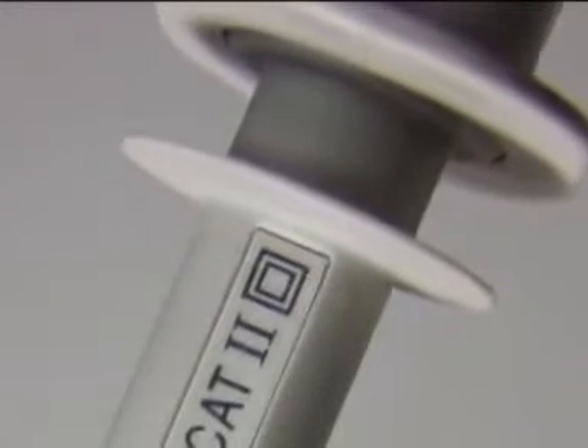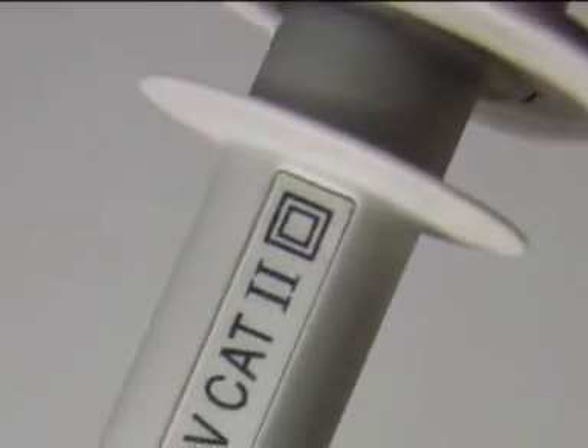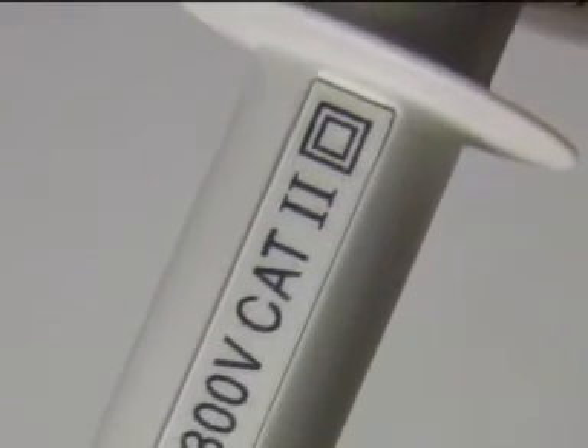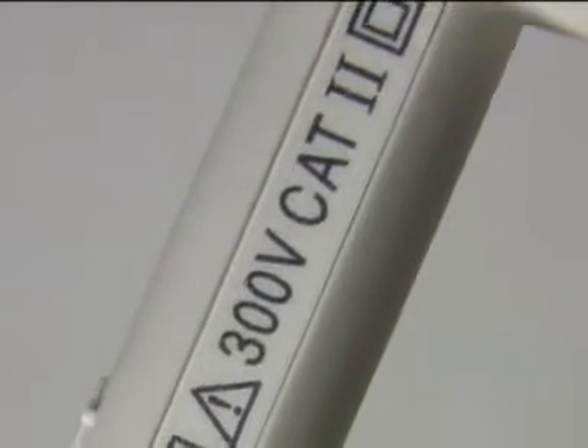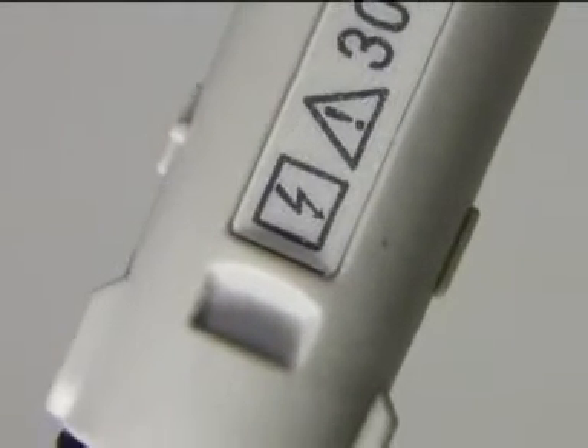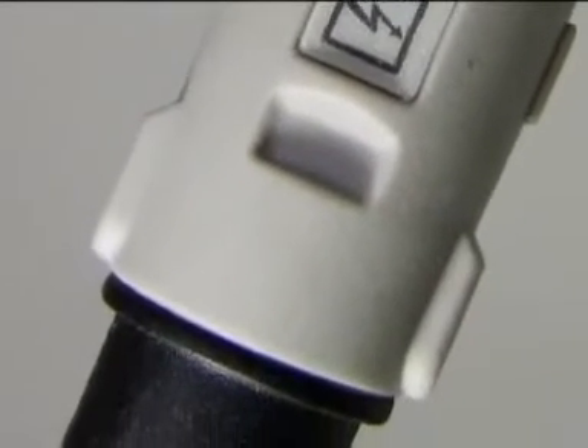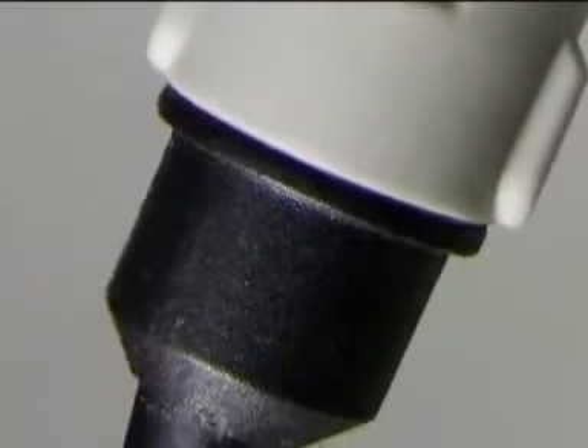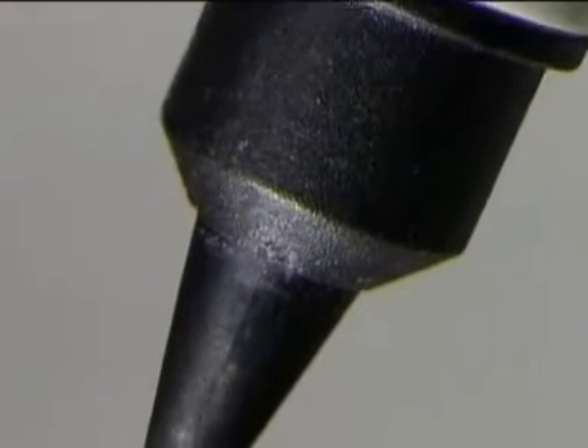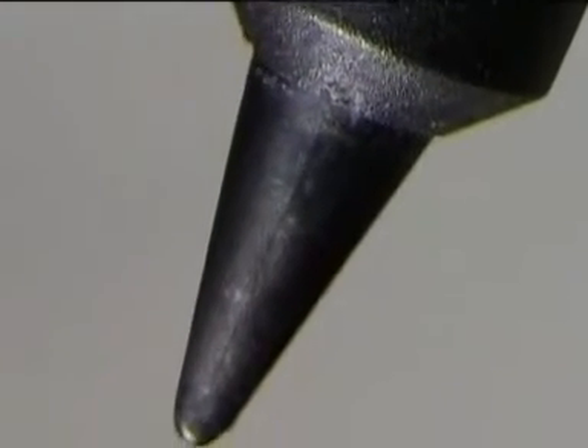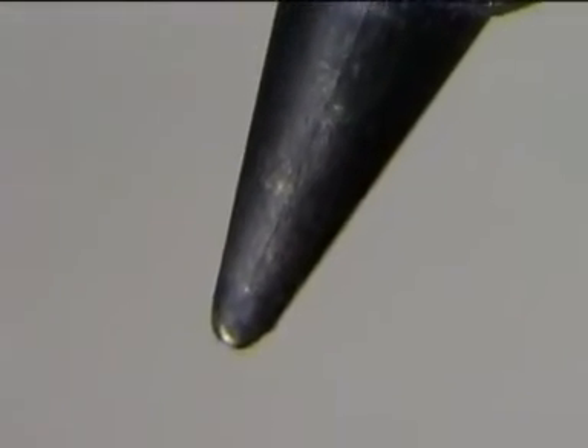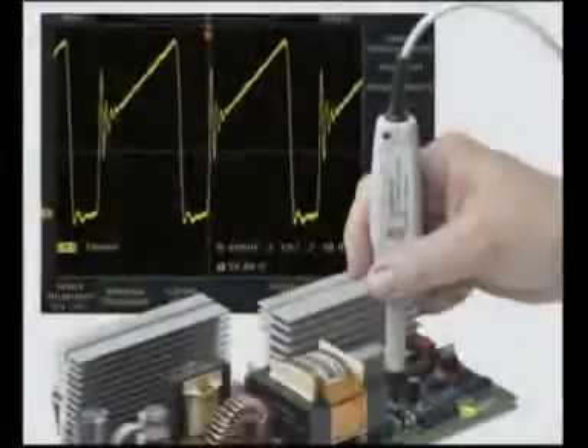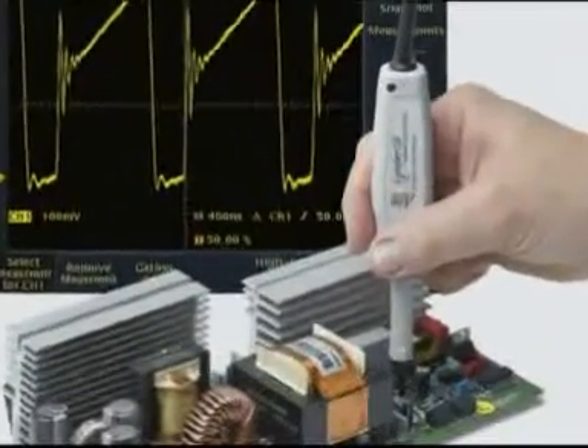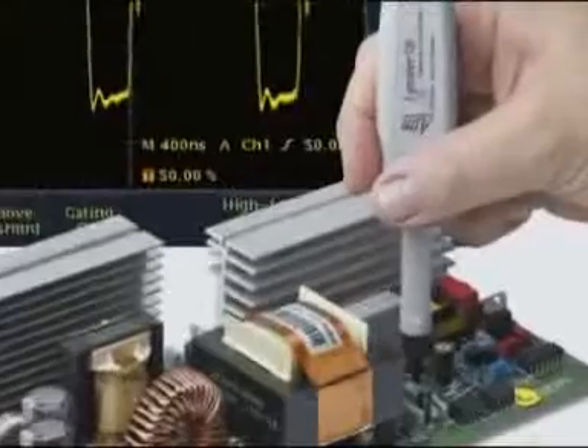So what's inside an iProber that makes this type of measurement possible? The heart of the probe is a patented miniaturized version of a fluxgate magnetometer. Fluxgate magnetometers have been around for decades, but not in miniature form. It is the patented miniaturization that enables it to measure the field at a precise point in space. But in addition to that, the miniature sensor has a much lower noise and much wider bandwidth than a conventional fluxgate magnetometer. Users must consider all fields that will be present in the area of the probe tip.